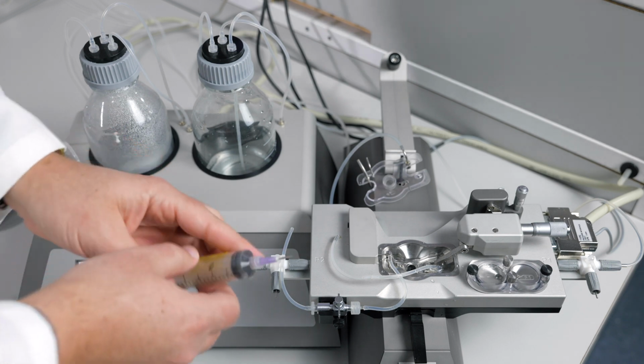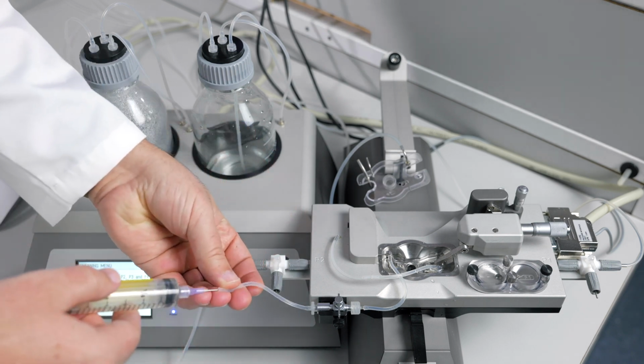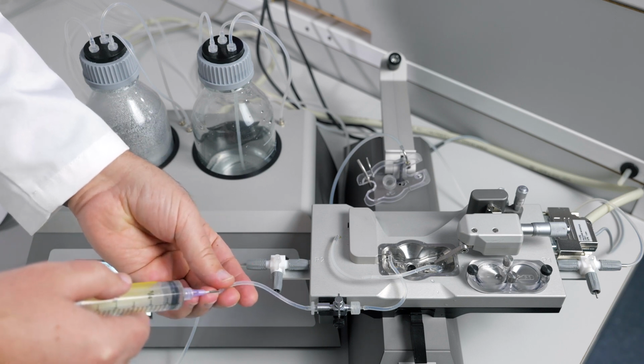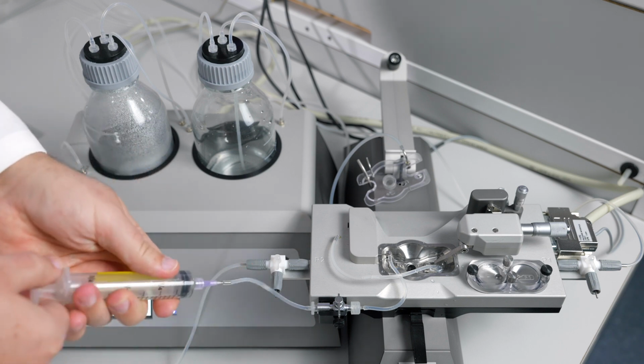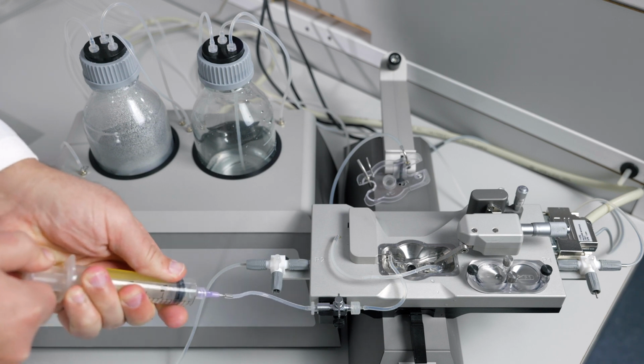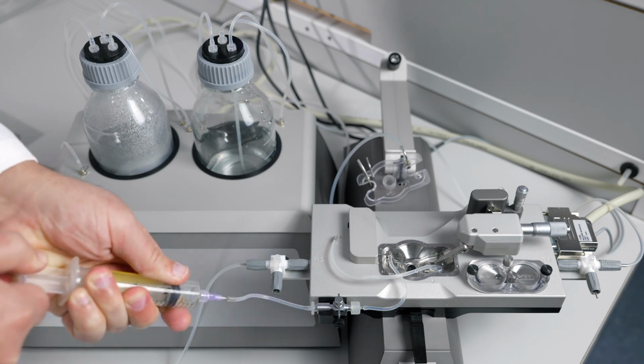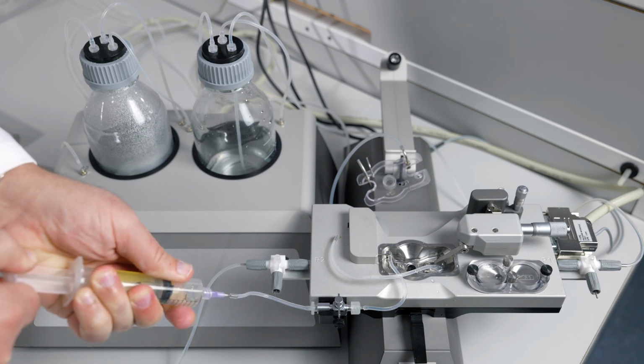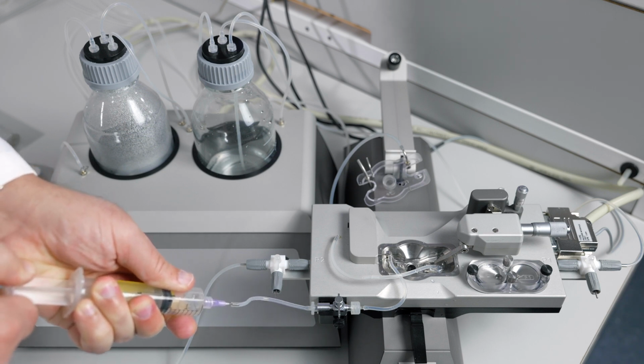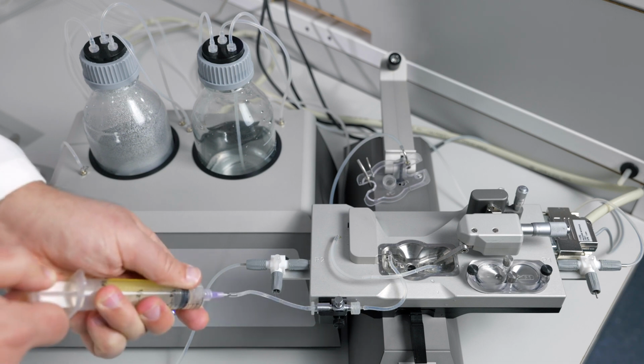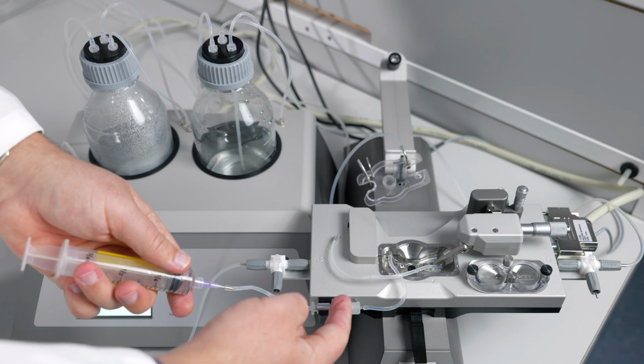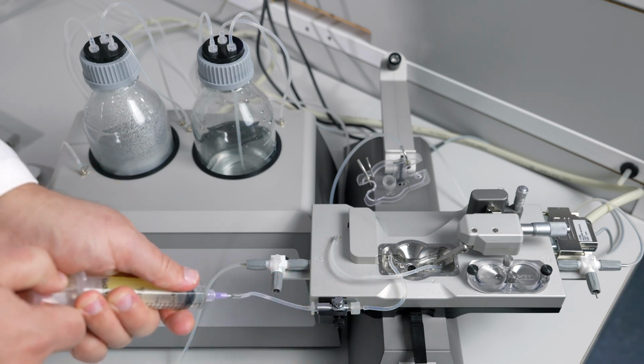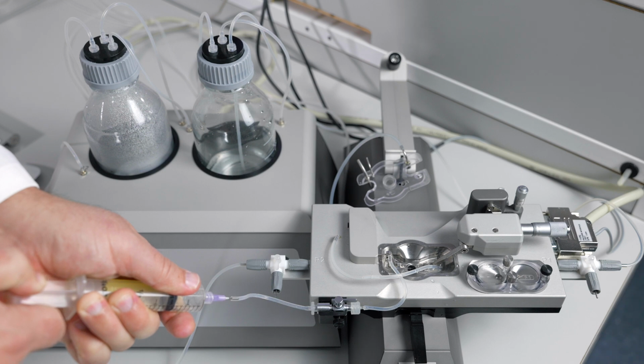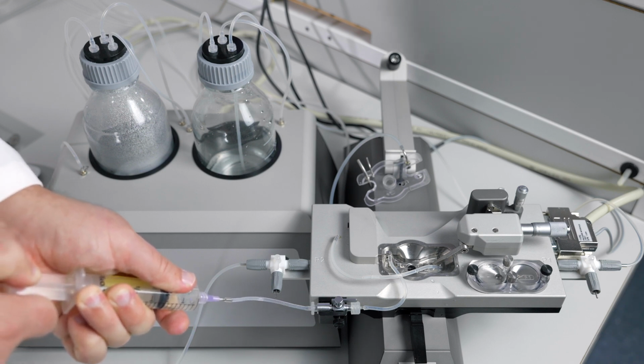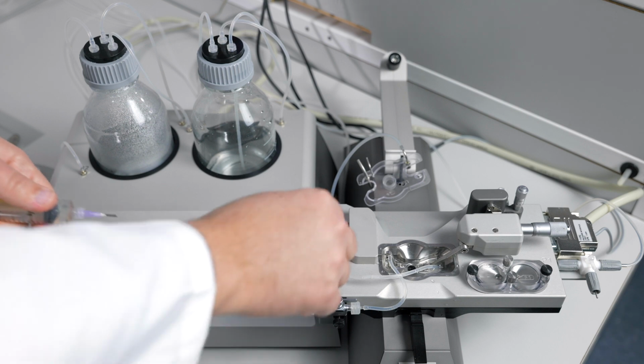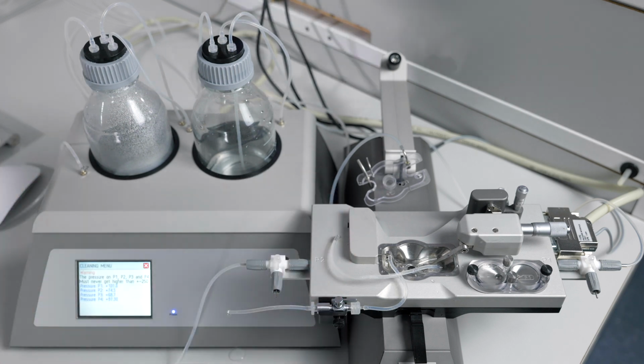Now take a syringe with a blunt-tipped 18-gauge needle to draw buffer back into the P1 and P2 cannula tubing. Since you are not going through the pressure transducers, you do not have to worry about being too forceful. Make sure that the valve is in line with the flow to allow you to pull this water back. We can now empty the chamber of all remaining water.